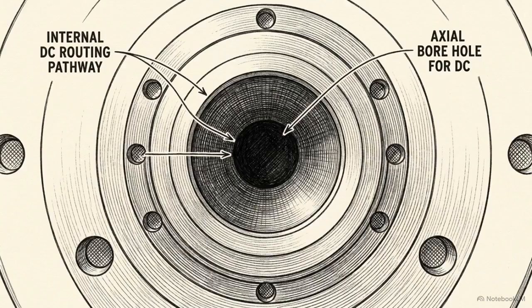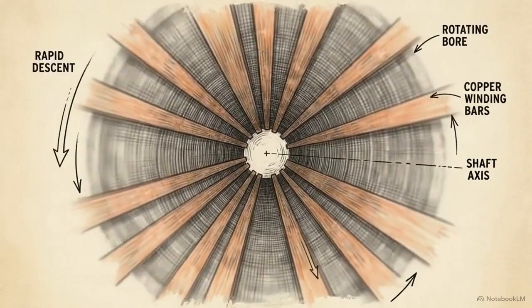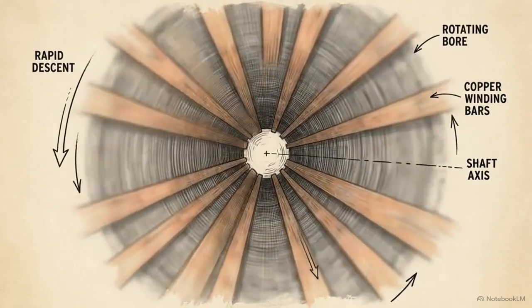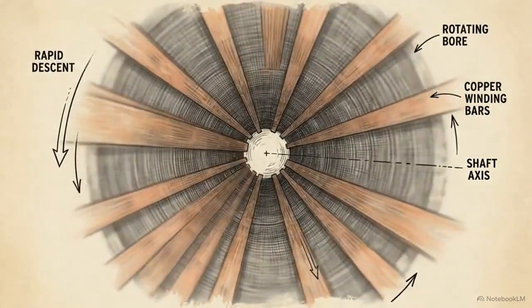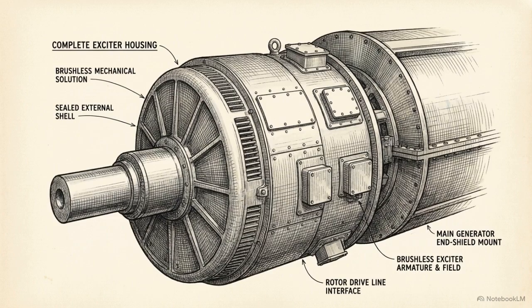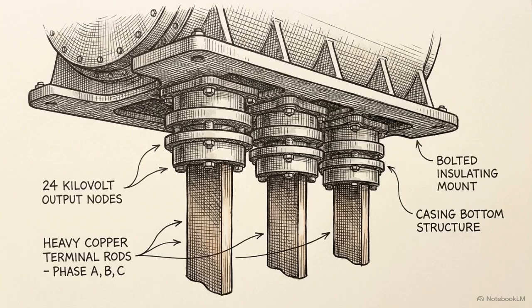The resulting 7,600 amp DC current is then routed straight down an axial bore through the center of the main shaft, flowing along the flat copper bars directly into the generator rotor. Brushless excitation solves the mechanical friction problem entirely by generating and rectifying the necessary control power on the rotating mass itself. The induced 24 kilovolt output exits the stator via 3 heavy-duty line terminals located at the bottom of the exciter side.